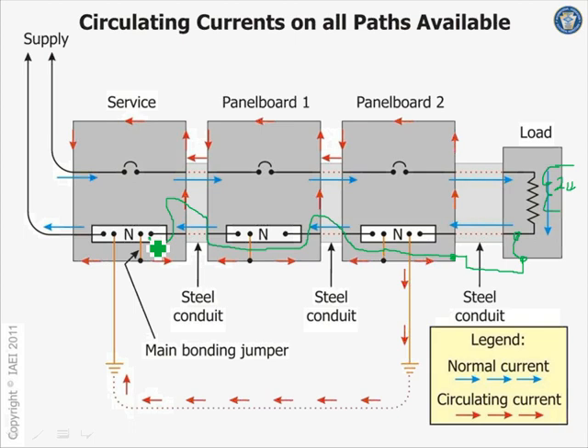I don't see it here though on a construction power system, because you're bonding this electronic equipment. You're taking it all the way through the grounding system and taking it back to the source. But that conductor could be carrying current though, the equipment ground conductor. But did you say that you get rid of this little bonding here, or you keep it for the operation of the equipment? So the rack is getting its ground from an isolated conductor all the way back to the building. Okay, fine, but what happened to the actual? Okay, that's coming through the plug though. Yeah. So the rack is going all the way back, and this one is also coming from an isolated ground.